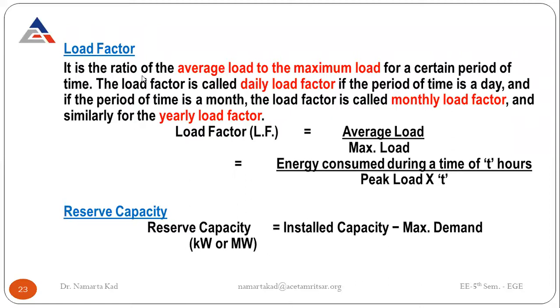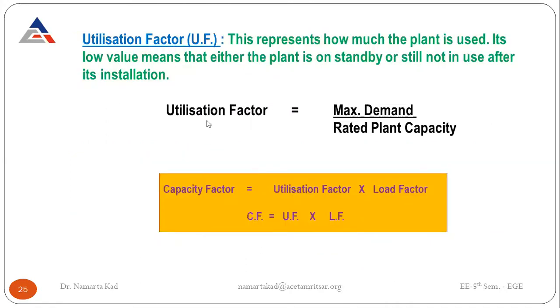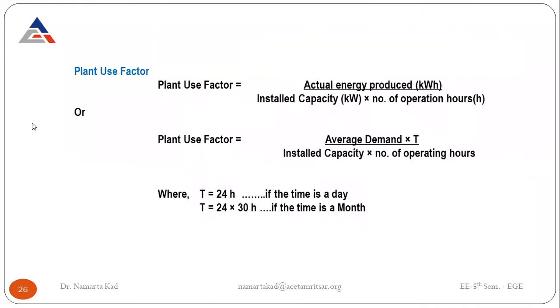These are some definitions covered in our last lecture. Load factor is the energy consumed during time T hours divided by the peak load into T — T depends on whether we calculate load factor yearly, monthly, or daily. Reserve capacity is installed capacity minus maximum demand. Plant capacity factor is average demand divided by rated plant capacity, or using the formula: maximum load divided by plant installed capacity multiplied by load factor. Utilization factor equals maximum demand divided by rated plant capacity, and their interrelation is: capacity factor equals utilization factor into load factor.